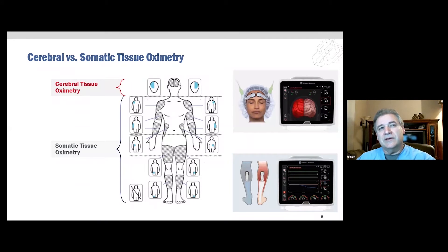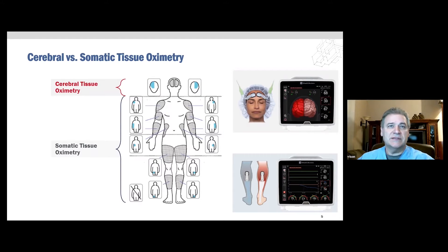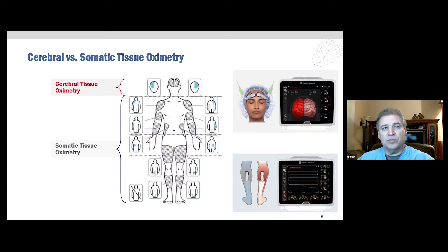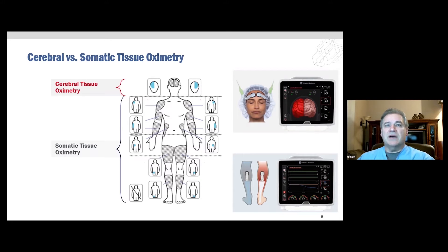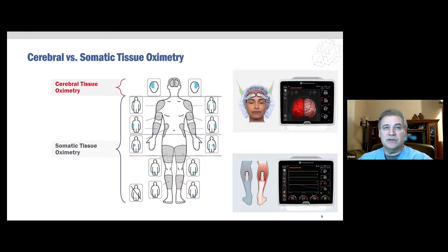The NIRS system we use is the Edwards Foresight Elite System. One of the reasons being is that it possesses an algorithm that is tailored to the unique optical properties of both cerebral and skeletal muscle sites. It compensates for the effects of skin pigmentation and melanin. And as an absolute tissue oximetry device, these sensors can be applied at any time, whether the patient is anesthetized or not.